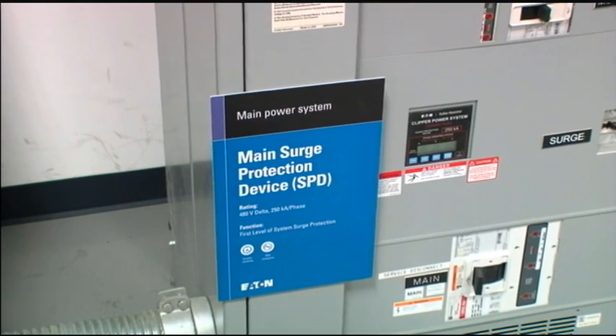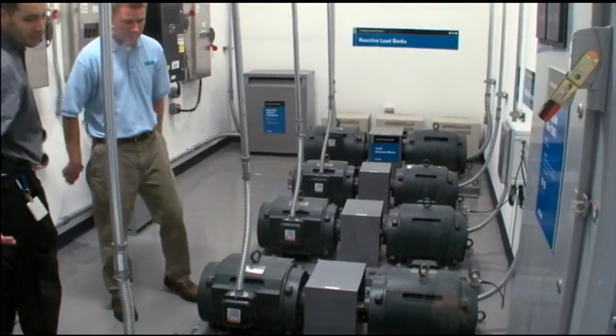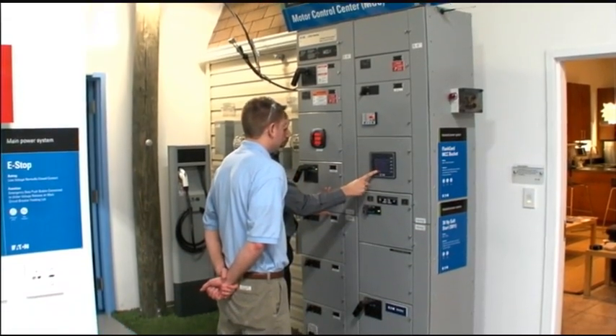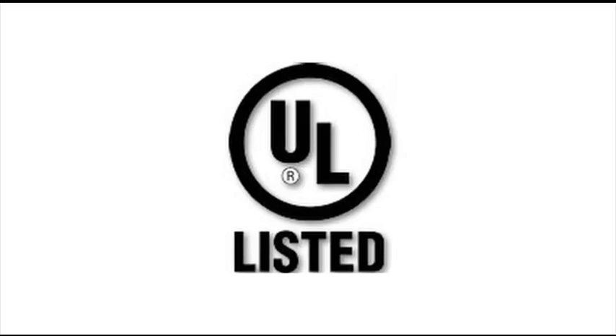Typically, you want to have a two-stage approach to installing surge protection. Your first stage should be at your main panel to capture transient and lightning events coming into your facility. Your second stage should then be used on your subpanels to lower the let-through voltage from the first stage down to a level at which it will not damage equipment attached to that second stage. Also, you want to make sure that anywhere you have equipment generating transients — such as load switching devices — there are two stages of surge protection between that transient-generating equipment and any sensitive equipment.